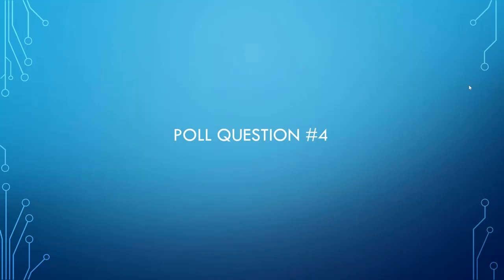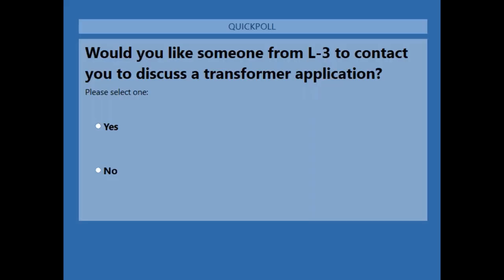While he's doing that, one bit of trivia for those that are not utility customers. I get asked a lot, why would I specify YY versus a Y delta or a delta Y? With the delta Y, you're going to get a phase shift. And the reason utilities use a YY is they can change all these different voltage levels and not have to worry about a phase shift in the transformers. So that's one of the big differences.